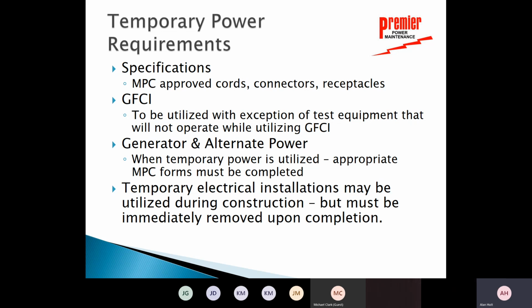If you have a generator and alternate power, so if you're using temporary power to keep some of their equipment energized, this is different than just operating our test equipment. If they're doing alternate feeds, tying systems together, or if they set a generator up to operate certain aspects of their business, then there has to be an appropriate form filled out, an MPC form that has to be completed. And then, if we're ever involved in temporary electrical installations, they can be used during construction, but they have to be completely and entirely removed the minute that construction is done.